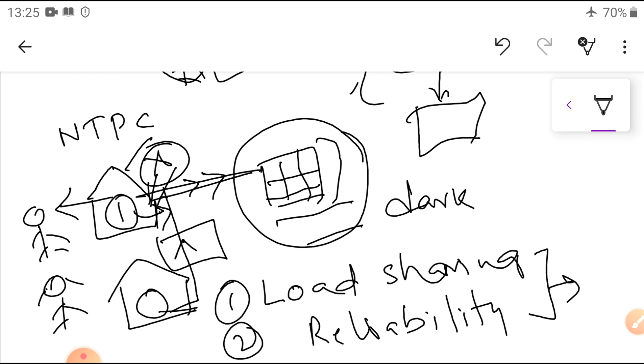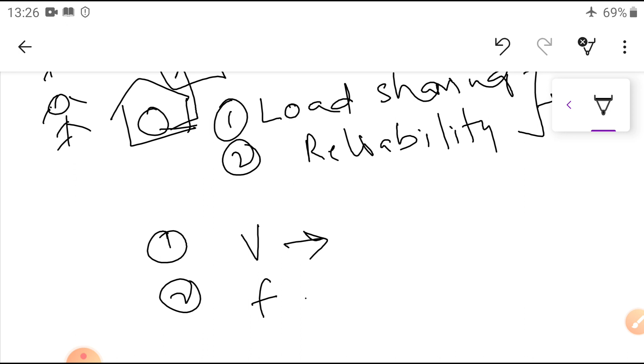The first condition is that the incoming system and the already existing system's terminal voltage should be equal. The existing system voltage and incoming system voltage should be equal. At the same time, the incoming system frequency and the existing system frequency should be equal. That means the busbar should be 50 Hz plus or minus 5%, and the incoming system also within 5%. That is, the frequency of the incoming alternator must be equal to the busbar frequency. That is the second point.